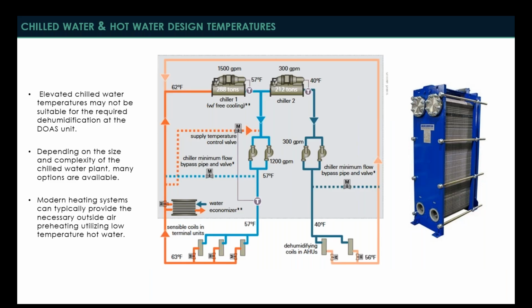Another thing I wanted to mention is the chilled water and hot water design temperatures. We mentioned that we're using elevated temperature chilled water and low temperature hot water. Well, on the hot water side, that may not be too big of an issue. Typically in today's modern systems, you can use low temperature hot water at both the air handling unit and your sensible cooling device, radiant panel or radiant floor, without much of a problem. But on the chilled water side, because we have to maintain that dehumidification, 55 to 58 degree water is not going to be cold enough to do the dehumidification that you need to do.